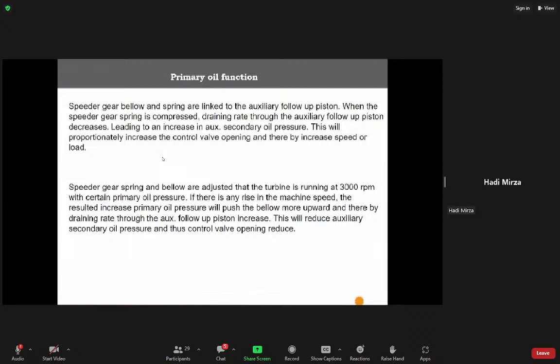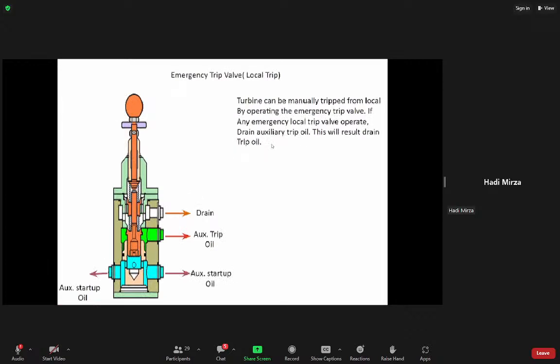Emergency trip valve. Basically, the main trip valve converts secondary oil into auxiliary trip oil and trip oil. In local also, you can trip the main trip valve by tripping this lever. You can trip the turbine. Basically, what happens while we trip this main trip valve? Oil from the auxiliary trip oil will be drained from here. This port will be connected to drain, and actually when it is in reset condition, auxiliary trip oil pressure will be kept on hold here.